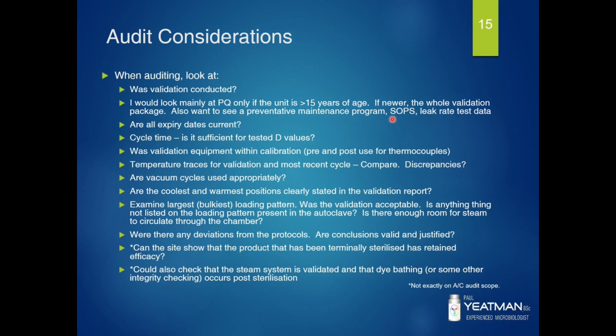The auditor would also be looking for SOPs and OIs and leak rate test data, basically all the supporting documentation needed to run the autoclave. You'd be looking at expiry dates. Are they current? So when was the last time the autoclave was validated? Is that aligned with your validation master plan and your SOPs? Was anything autoclaved post-expiry of your validation, and if so, what is the impact? So there should be an investigation into the impact of something that deviated from the established procedures.